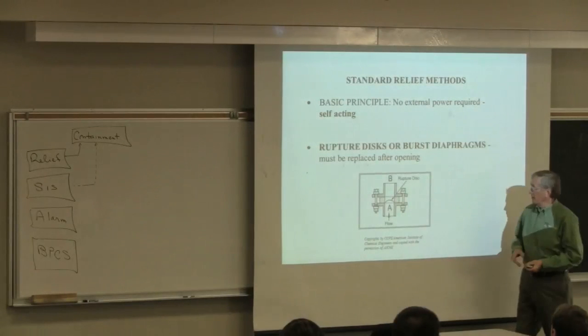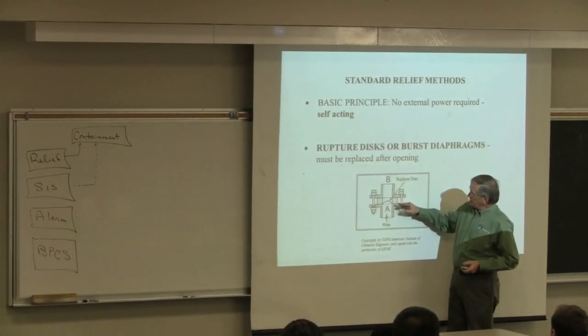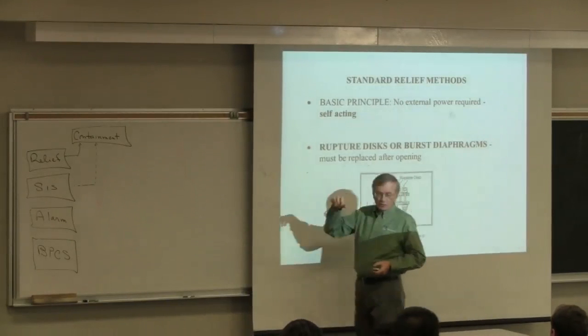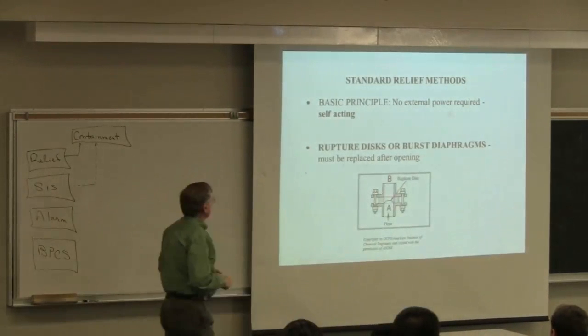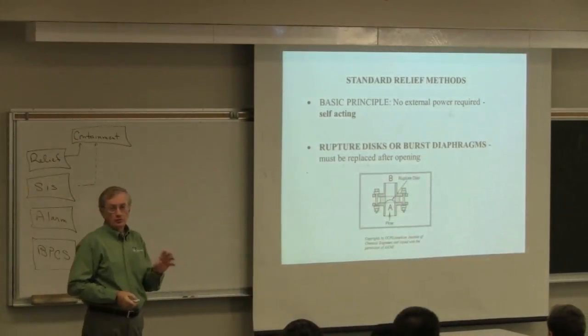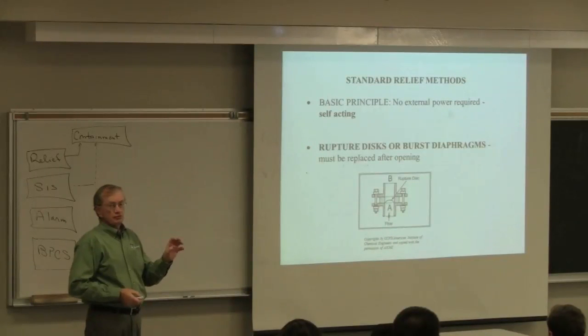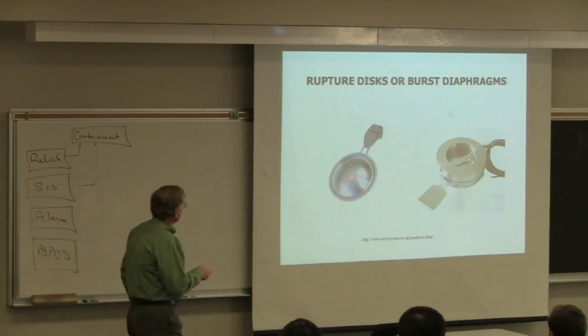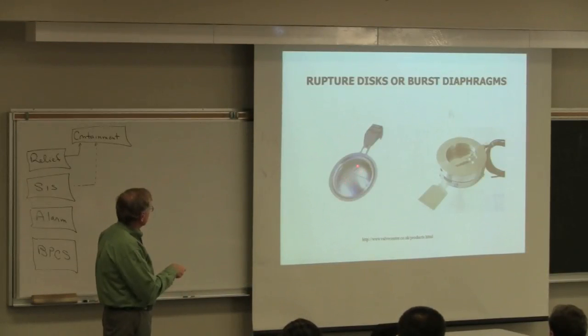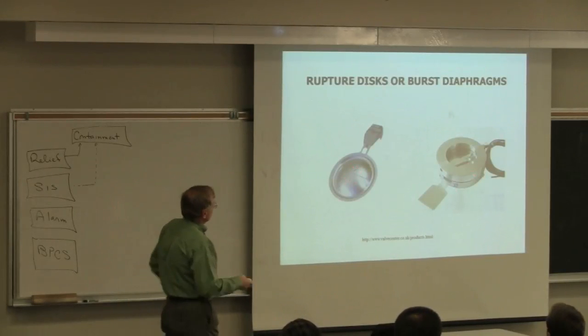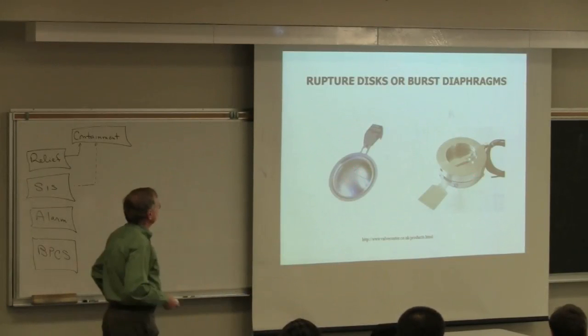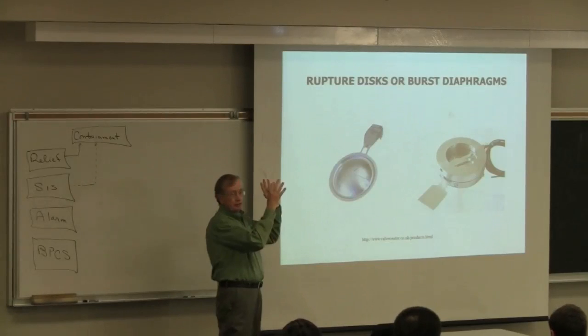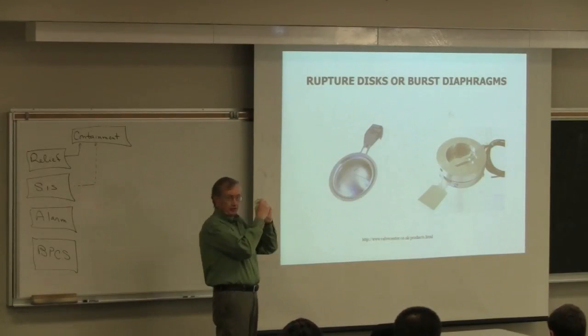The rupture disk is a metal device inserted in a pipe—it's the weak link, the weakest part of the mechanical system, engineered to break at a certain pressure. You have to buy these disks from the manufacturer. You can see scoring on the disk surface to ensure it breaks at a certain point. It's installed between two flanges. Once a rupture disk breaks, it doesn't reseal, so you have to shut down the process and replace it.